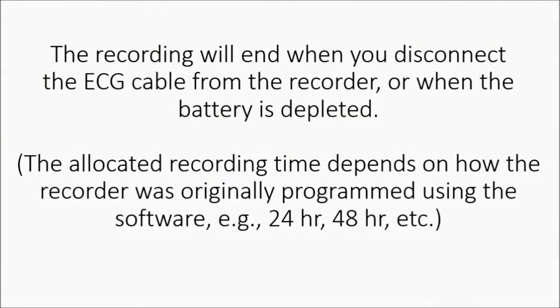The recording will end when you disconnect the ECG cable from the recorder, or whenever the battery is depleted. Note that the recording time available depends on how long the recorder was originally programmed.